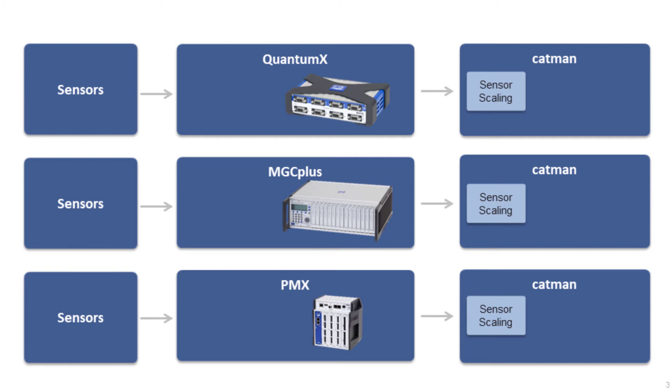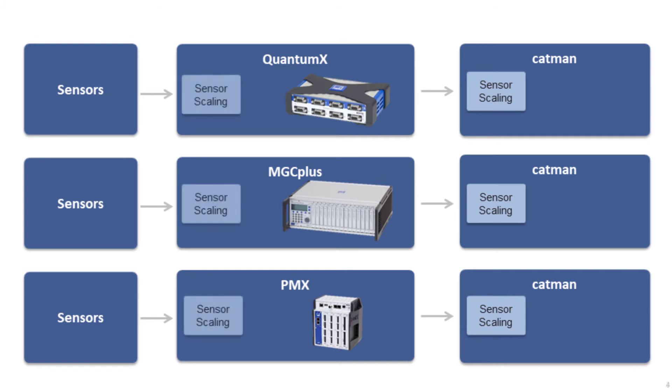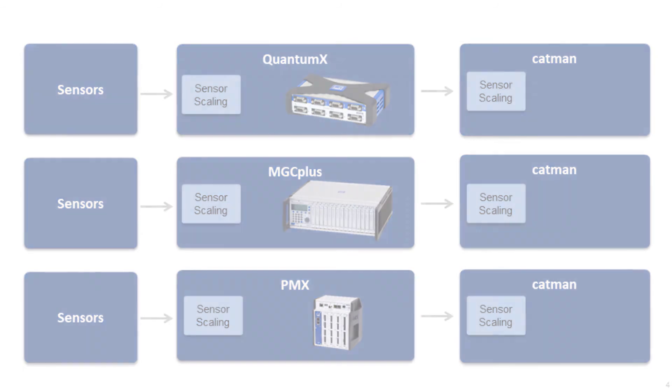However, this is only essential if you want to output the measured values within the hardware Quantum X, MGC Plus or PMX via CAN, EtherCAT, PROFINET, an analog output or the AB22A. If this is important to you, create a scaling in the sensor database that is supported by your hardware and create another scaling in the online calculations or the calculations in analysis mode.